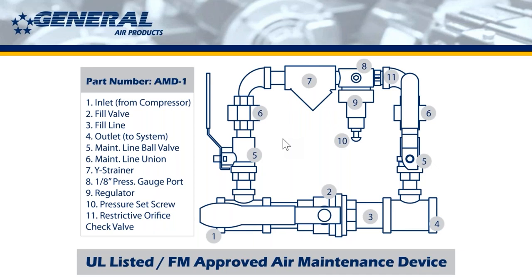Another thing I want to call out here is the Y strainer itself. You see this part here that goes down, hopefully you can see my cursor. This is a trap for debris. So we get questions a lot of the time about whether we can orient the AMD1 upside down instead of the orientation that we're looking at here. The only problem with that is that the Y strainer, which is supposed to catch debris and prevent it from getting into the regulator, is now facing up, and no debris is going to be caught in there.